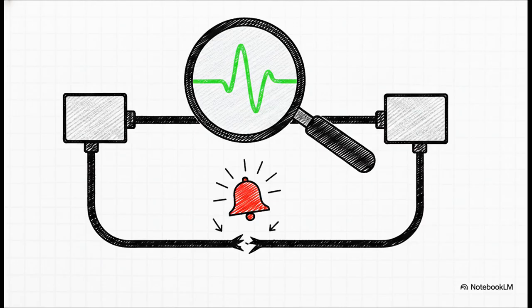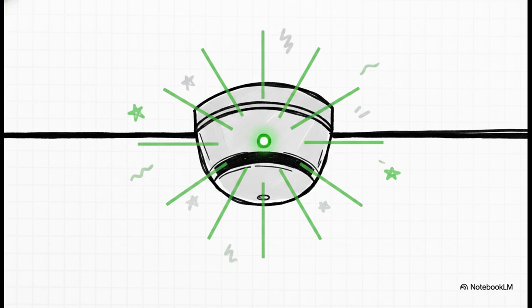It runs a continuous tiny test signal right through the trip wiring. And it's incredibly smart. It uses different electrical paths depending on whether the breaker is currently open or closed, meaning it leaves absolutely zero operational blind spots. If a wire breaks or control voltage drops, it doesn't wait for a fault, it triggers an immediate alarm. Think of it like the small green power-on light on your smoke detector at home. It doesn't wait for your house to catch on fire to prove that the detector has power. It continuously confirms its readiness. Having that continuous confirmation is just vastly superior to waiting for an actual emergency to test your equipment.